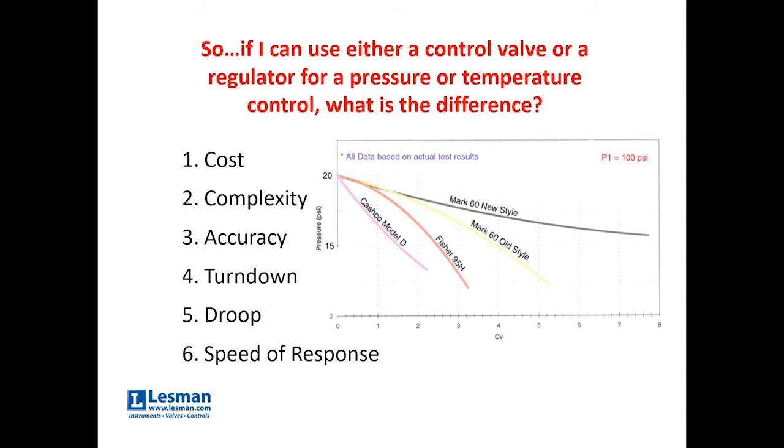Cost, obviously, a control valve is more money because there are more components involved. You have to have a PID loop, you have to have a remote instrument sensing the process variable, there's wiring involved, so a control valve is more costly. Complexity, obviously, the control valve loop is more complex.